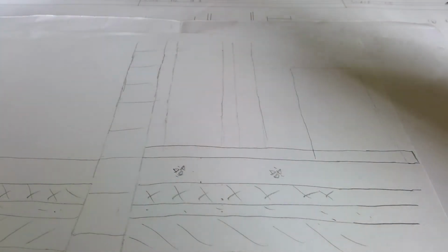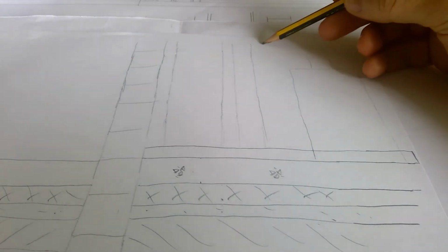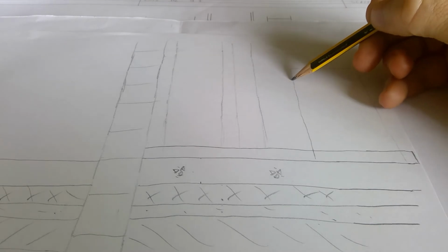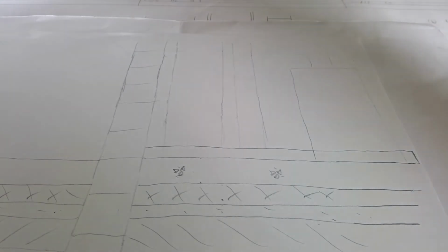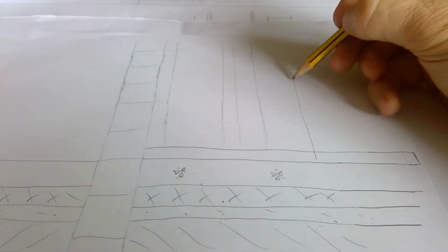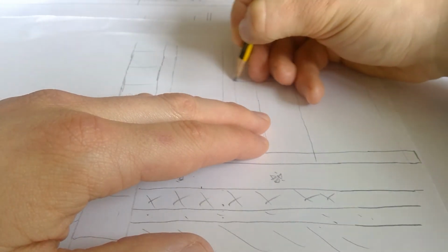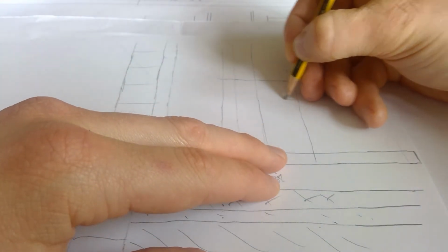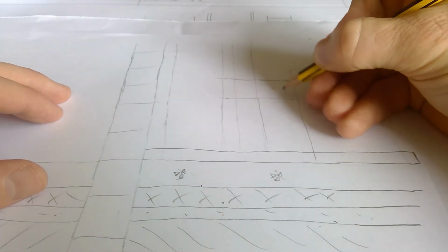Now when it comes to the flue liner for the stove, in the sketch you can see that the pipework comes up like that and across. It might leave you tight for space to get that in, but a lot of stoves have the pipework just come out of the back and up into the chimney as well. Either one is completely fine. There are different variations on how it's done, and I always prefer to do it out from the back and up through it. So just measure down a certain distance, make a judgment yourself there, and I'm going to draw the pipework in through there, 150 mil diameter. It says in the question, so that pipe is 150 millimeters in diameter.